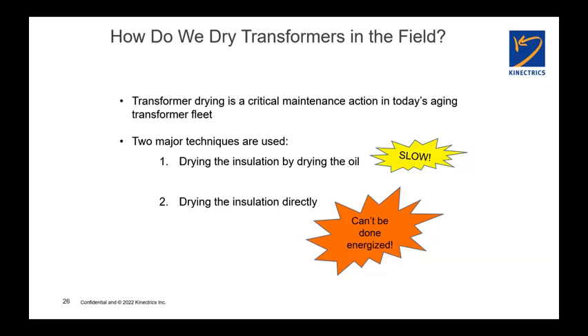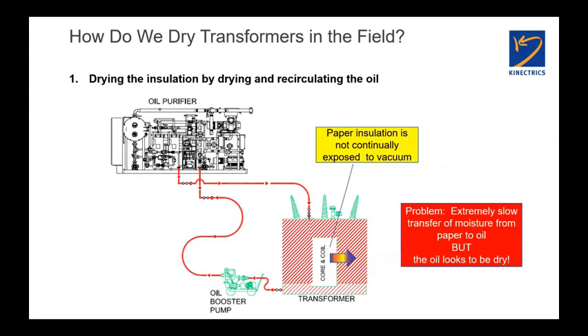We know that whatever water's in the unit is in the paper, not in the oil. So we can attempt to dry the paper by drying the oil and hoping that the moisture is going to come out of the paper into the oil where we can pull it out. Or we can dry the insulation directly. The problem is that can't be done with the transformer energized. By attempting to dry by drying the oil, this is just using a vacuum degasifier, an oil processor.